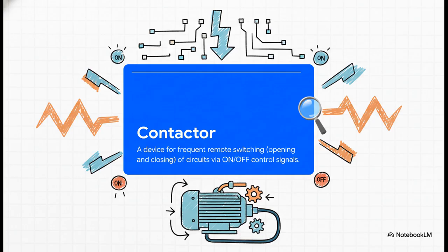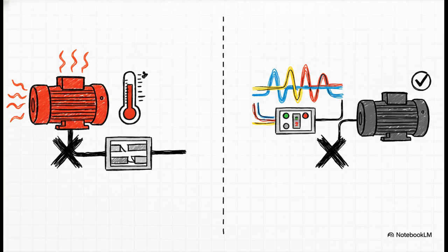Pretty cool. Low-voltage systems are really all about precision protection. They use specialized little gadgets for very specific jobs. For instance, a bimetal relay will protect a motor from slowly overheating, while a phase monitoring relay protects it from damaging voltage problems. It's all about making sure that expensive equipment lasts as long as it possibly can.